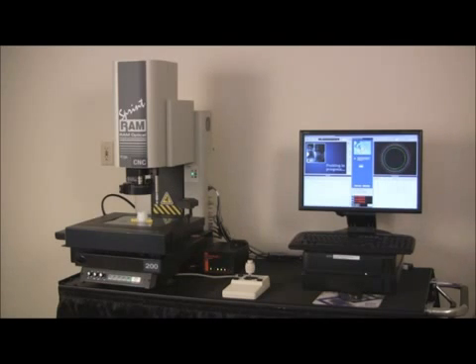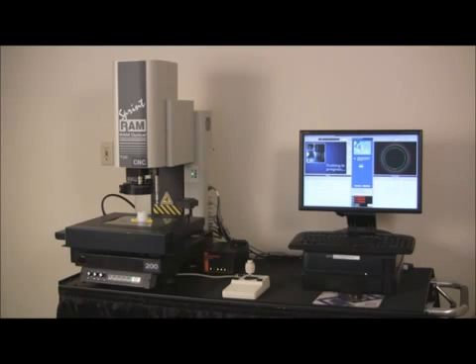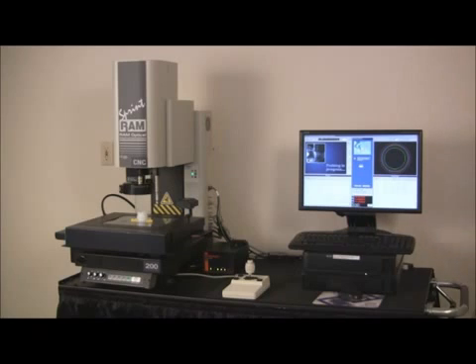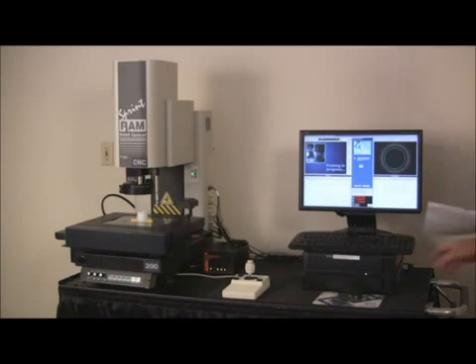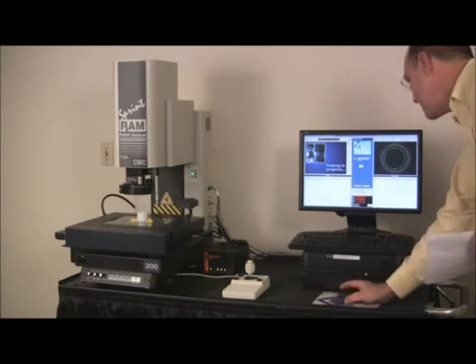What we're doing now is we're going to measure the ID of the bottle using the video and then we'll use the touch probe to measure the three diameters that require the six point measurements for roundness.